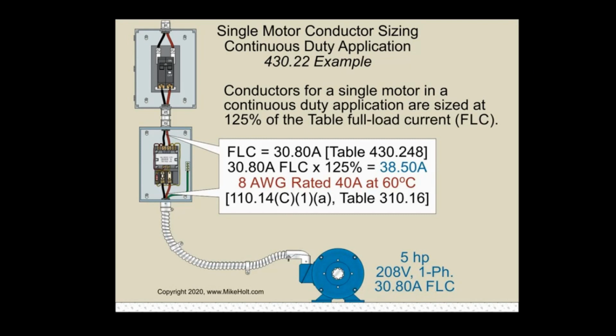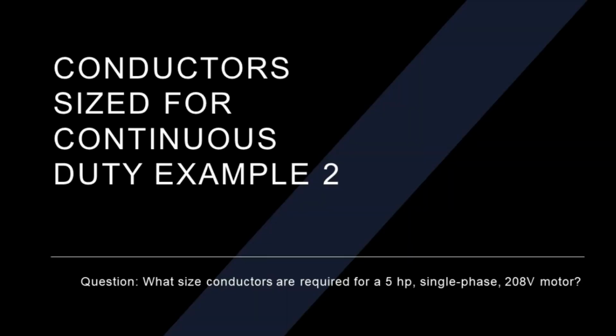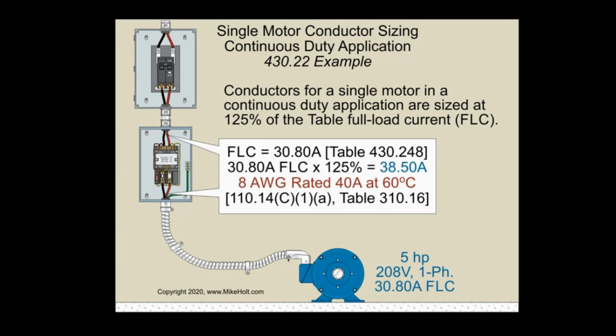Oh, I'm in the 60-degree column here, aren't I? So, conductors for a single motor in a continuous duty application size at 125% of the FLC, 30.8 times 125% is 38.5. 8 gauge, rated at 40 amps at 60 degrees Celsius. Okay. Eight gauge in the 60 degrees Celsius. I am not sure.